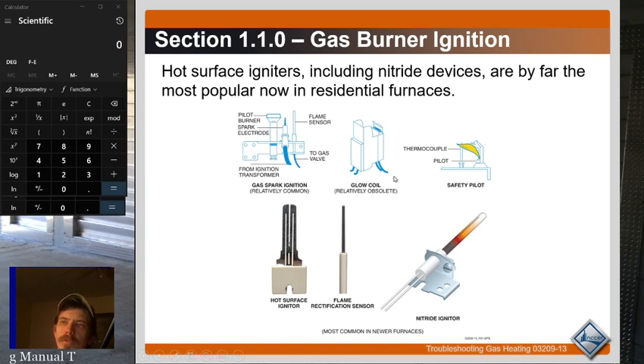Glow coils, basically think of glow plugs on diesel. That's pretty much obsolete now. Nobody does that anymore. A regular pilot, so that a pilot stays on all the time, and that's usually flame sensed through a thermocouple instead of a flame sensor. If you have a standing pilot, a thermocouple is generally used to prove that the pilot is staying on.